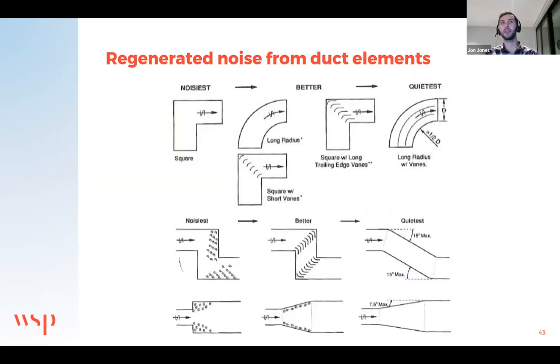This ties in with regenerated noise here in terms of ductwork layouts. Smooth transitions really are best for acoustics. They're obviously best mechanically generally as well, but the thing to note is where we do have abrupt changes of direction in ductwork, this does generate noise, which we need to consider. So where we have mostly on the right hand side smoother transitions, this is the best solution acoustically. Where we have these options on the left, the turbulent air generated as a result of significant change in either direction or shape is going to create turbulence in the airflow, which will generate noise, and it's also potentially going to impart energy into the ductwork, which again will radiate there and rumble away, which is not ideal.